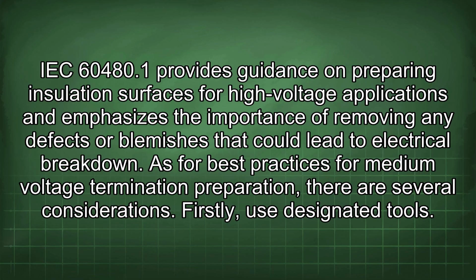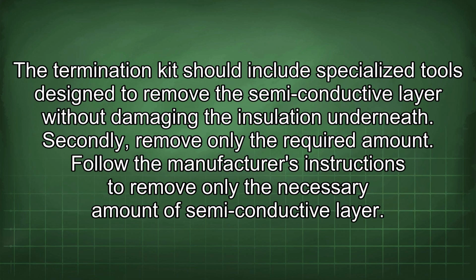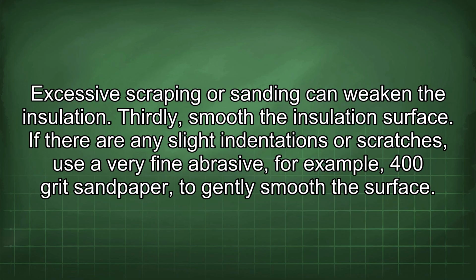As for best practices for medium voltage termination preparation, there are several considerations. Firstly, use designated tools. The termination kit should include specialized tools designed to remove the semi-conductive layer without damaging the insulation underneath. Secondly, remove only the required amount. Follow the manufacturer's instructions to remove only the necessary amount of semi-conductive layer. Excessive scraping or sanding can weaken the insulation.